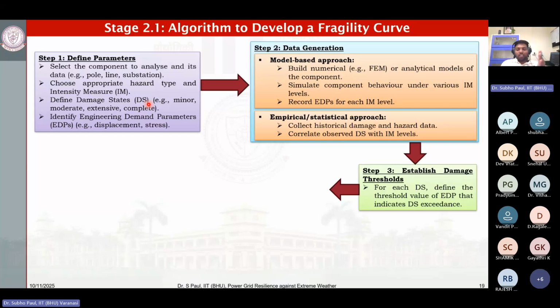So that threshold is specified, and from there, using different synthetic hurricane scenarios, you simulate those intensity measures for a particular equipment multiple times. You vary the intensity level, vary the scenarios, and do this study repeatedly, noting down the probability of failure - how many times the probability exceeds your threshold level.